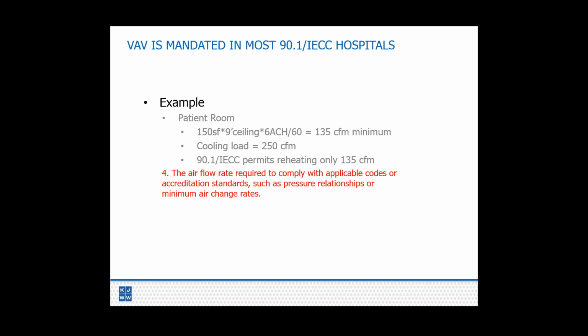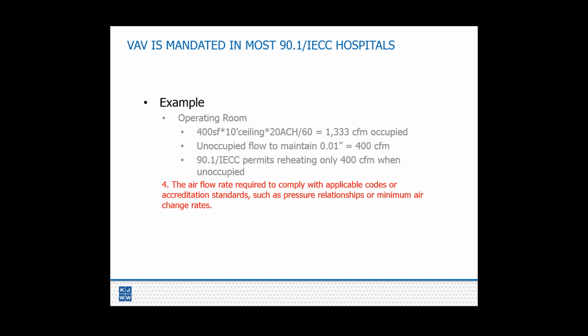So next slide, please. And I did another example with an operating room. Let's say you have a 400 square foot OR with a 10-foot ceiling, 20 air change requirement under ASHRAE 170 or FGI. So you've got about 1,300 CFM when you're occupied. Unoccupied, the only requirement is to maintain 0.01 inches. And in my example, I picked 400 CFM as what was required to satisfy the pressure controller. Yours may be higher or lower.